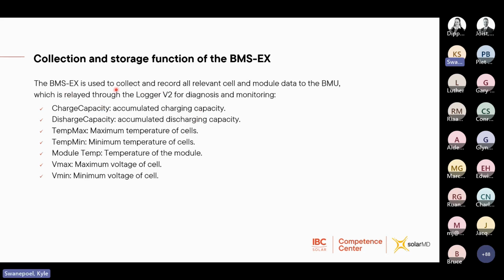Okay, so the information that gets stored to the BMU can then also be seen through the Logger V2, which is the SolarMD monitoring device, and then that can be viewed on the MyPower24 platform. This will then be the charge and discharge capacity of the battery. The minimum and maximum temperature of the cells also gets recorded and can be viewed in live time. The module temperature itself, as well as the voltage maximum and minimum for each cell in the battery, as well as per module.